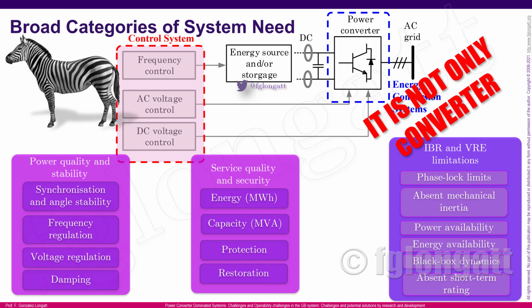What is important is that those power converters behave in a very different way. They require measurements like the phase lock - the PLL - which has some very specific and important behavior that affects the dynamic response of those systems. Also, there is no mechanical inertia. The power availability is a huge problem. The response of the power converter is inherently defined by the energy sources or storage used on the DC side of the power converter. It's very different compared with the synchronous machine.